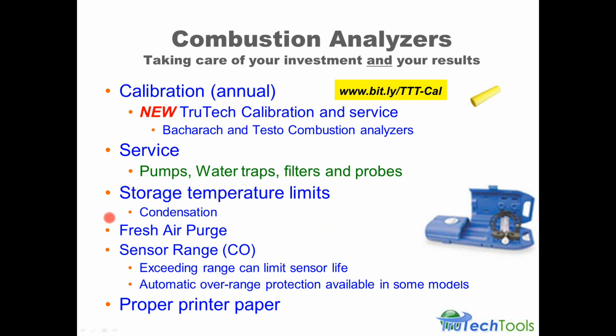You also want to pay attention to a fresh air purge. If your analyzer shuts down during the middle of the test, it may be the type that has an automatic shutdown sequence in it when it sees excessive levels of CO. And at that point, you're going to have to make sure that you don't overrange the sensor. I know some of the Testos have overrange protection, but if they do shut down, you immediately want to start them back up breathing fresh air. Or if you see your Bacharach go over range, you want to make sure that you get the probe out of the stack breathing fresh air, because you can cause a CO sensor to get drunk and actually kill it if you give it too much CO exposure. So you do want to pay attention to sensor overranging.